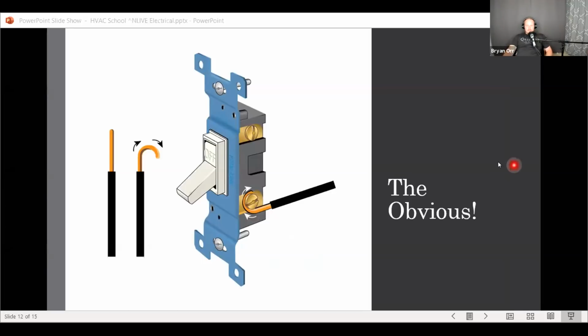There's a lot of different things that are just obvious diagnostic no-nos that an experienced technician keeps their eyes open for, that a newer technician often will miss. And from a diagnostic skill standpoint, that is a really invaluable skill. And also, just never allowing these little details to pass by the wayside. Double lugging is a really big one, where people take multiple wires and jam them underneath a lug where you're not getting good connection. All of those things can add resistance to the circuit, which can then cause problems because it causes voltage drop. Additional resistance causes voltage drop, which is part of what I was describing there. It's the same thing when you have a switch that starts to get carboned up, like a contactor, that can add voltage drop to the circuit and cause problems.